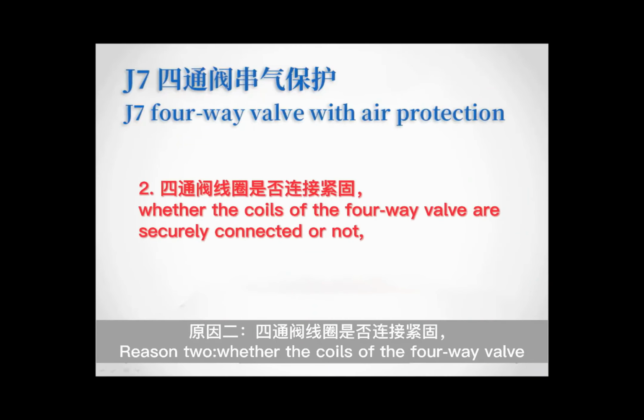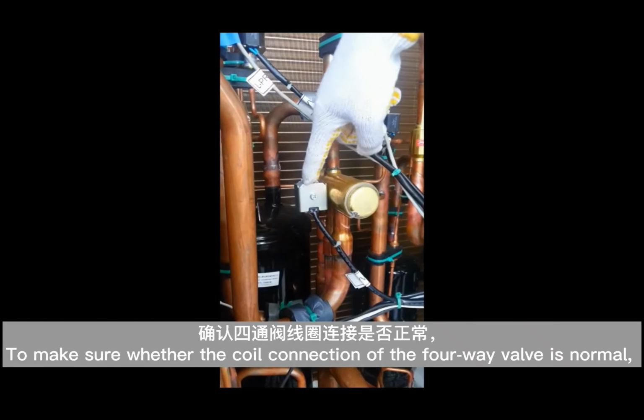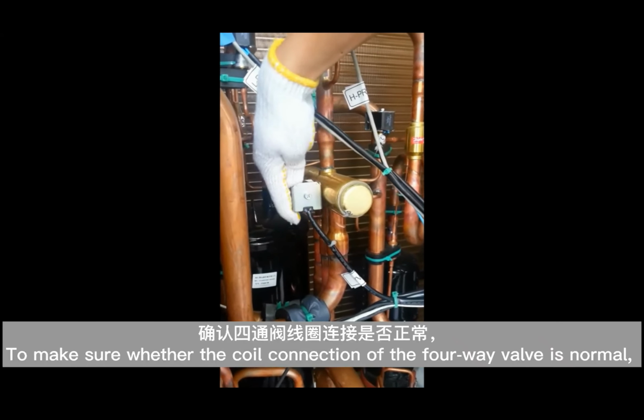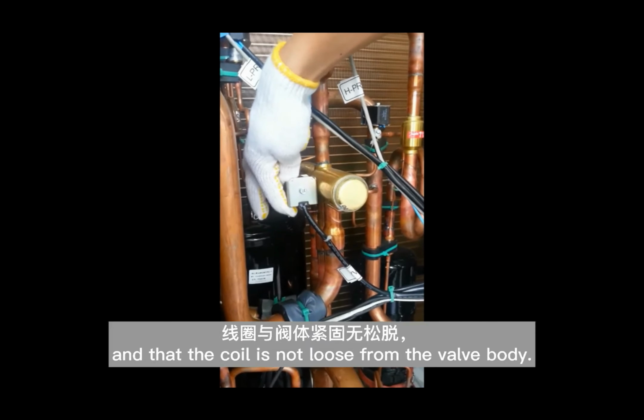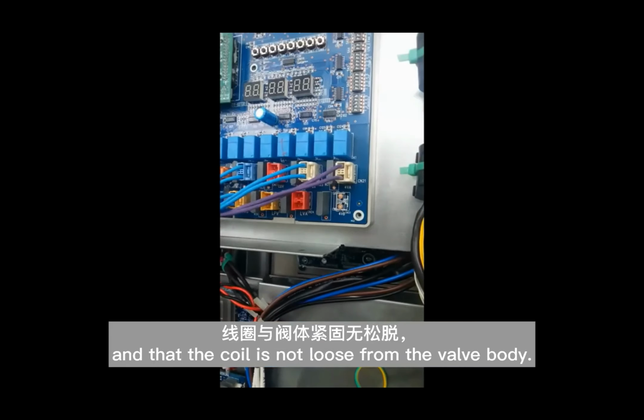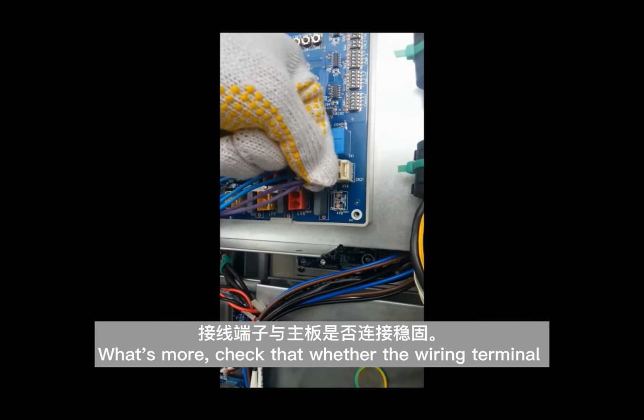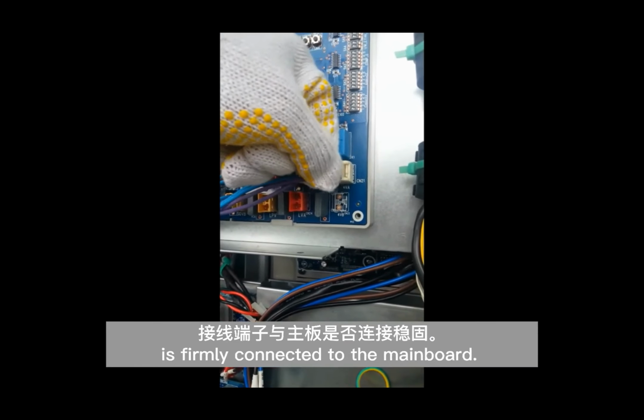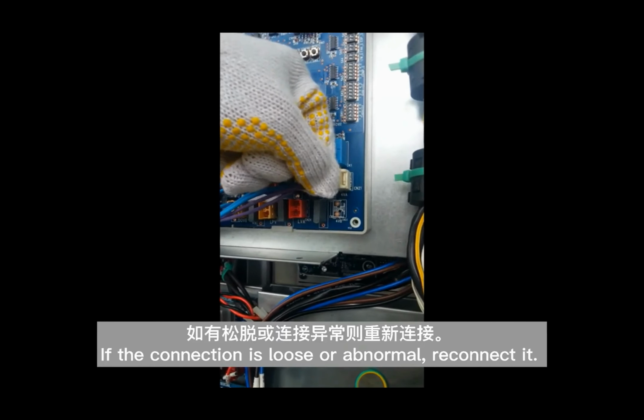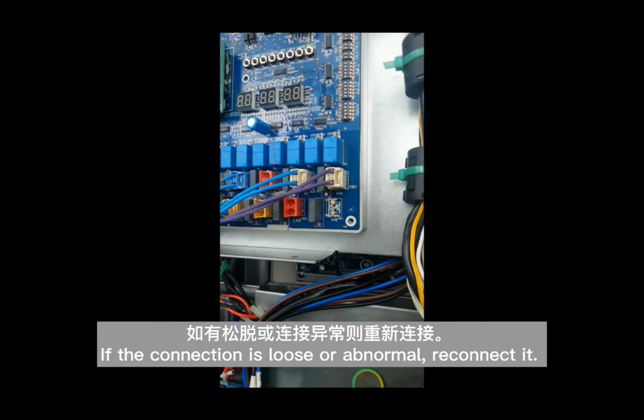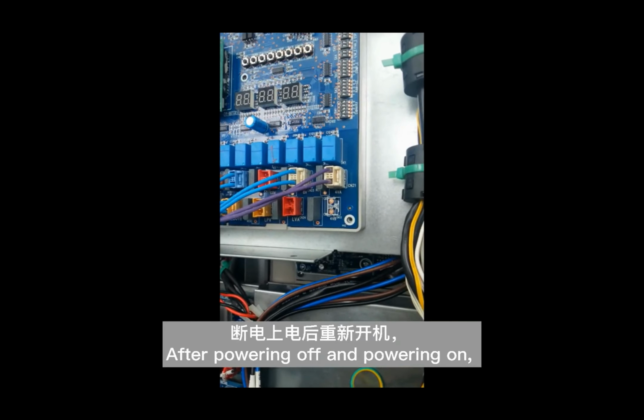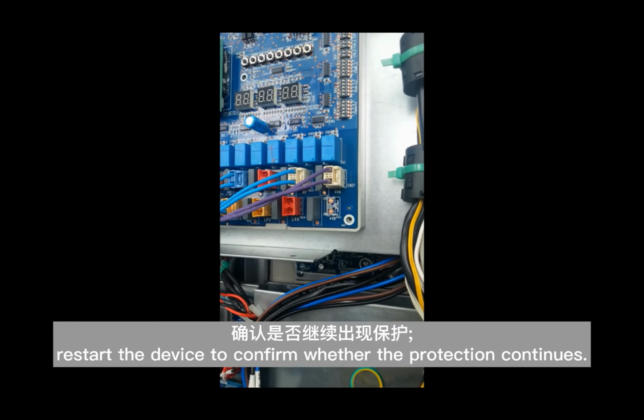Reason 2. Whether the coil of the four-way valve is connected tightly. So make sure whether the coil connection of the four-way valve is normal, and that the coil is not loose from the valve body. What's more, check whether the wiring terminal is firmly connected to the main board. If the connection is loose or abnormal, reconnect it. After powering off and powering on, restart the device to confirm whether the protection continues.